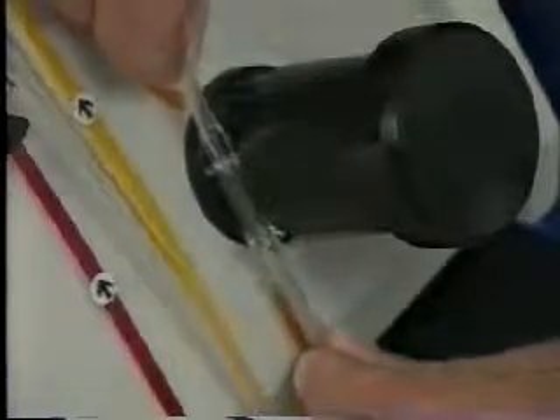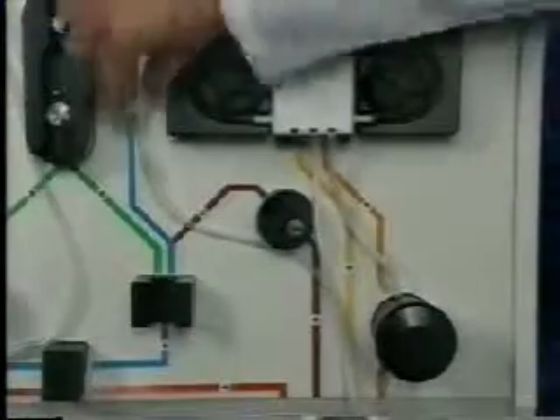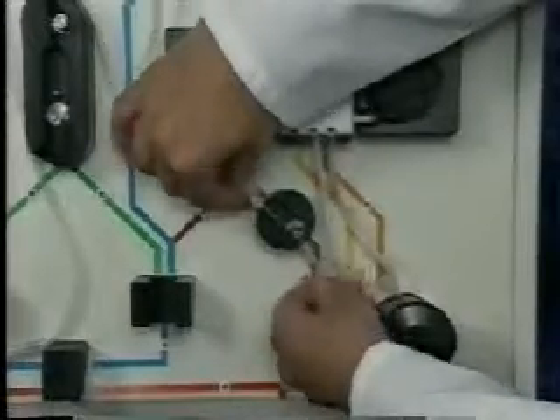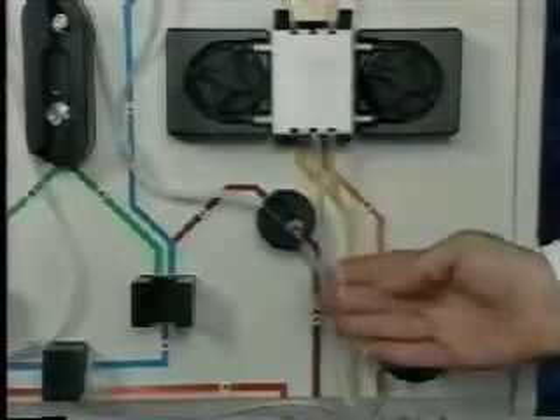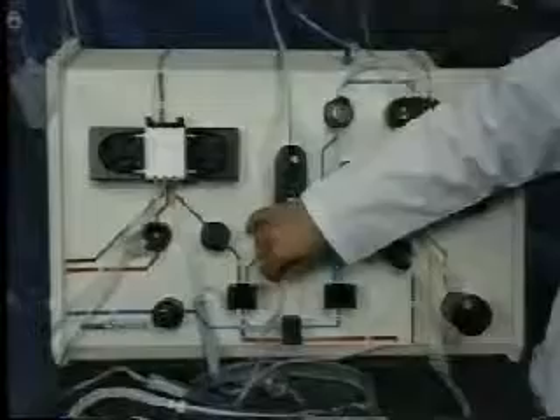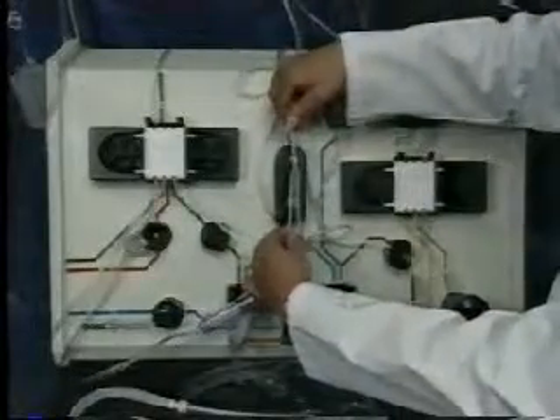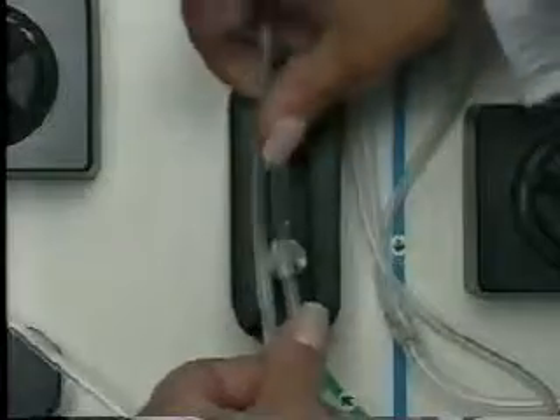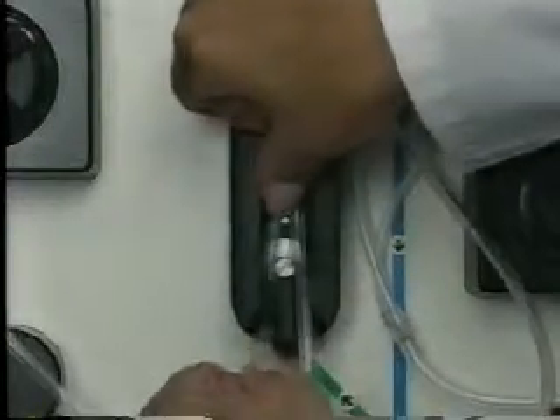While holding the tubing on both sides of the cuvette with a flat side parallel to the front panel, slide the cuvette into position. Turn the housing clockwise and lower it over the cuvette. Next, we need to load the RBC line into the RBC valve and detector. Ensure that the line going to the plasma pump is not loaded in the RBC valve. Insert the waste divert lines into the waste valve assembly and pull down on the lines to seat the Y connector on the pin.